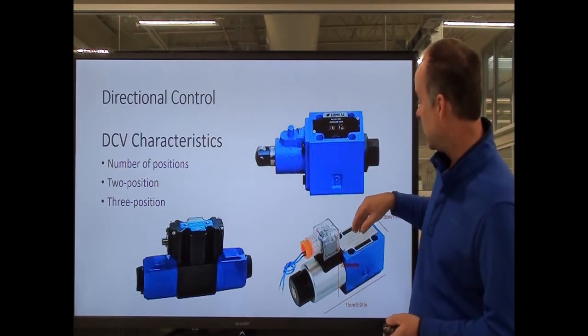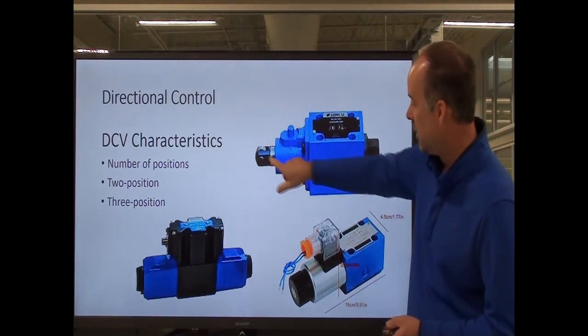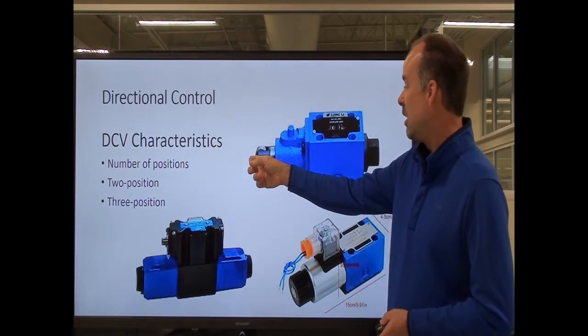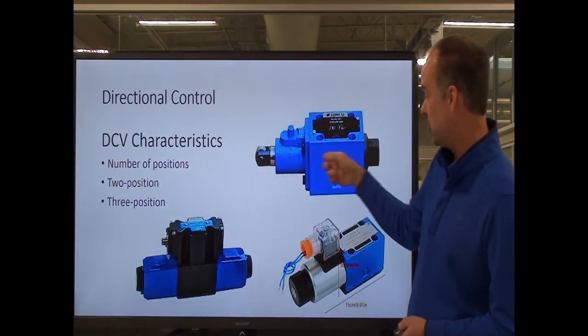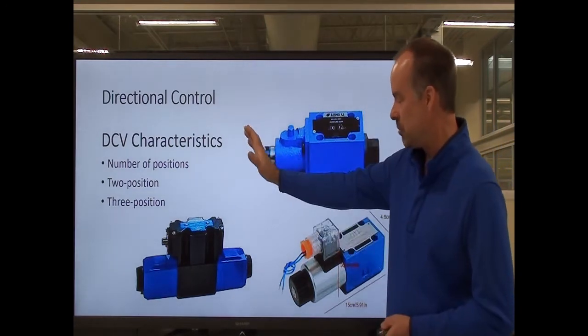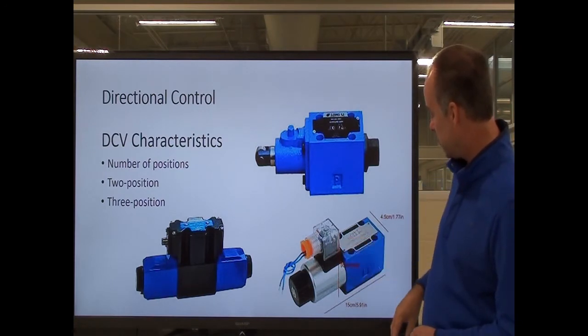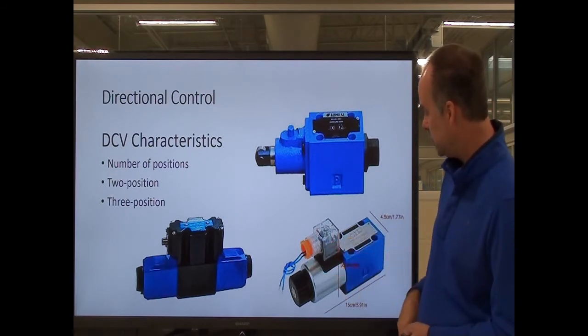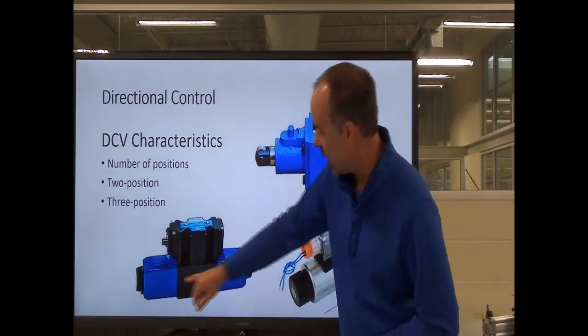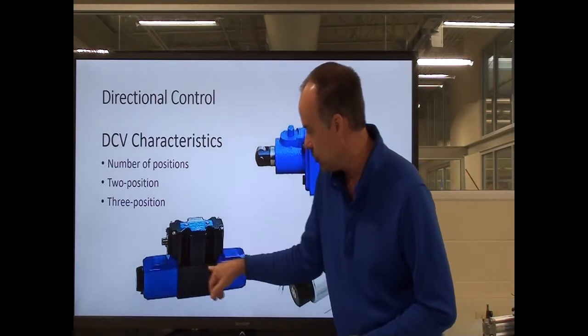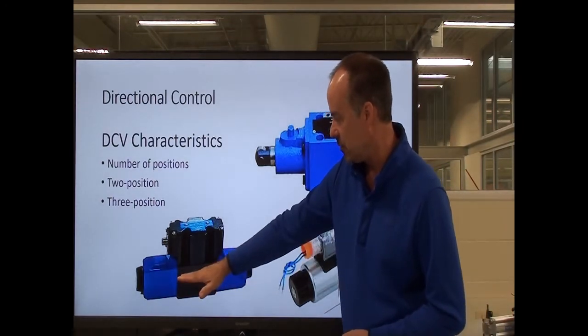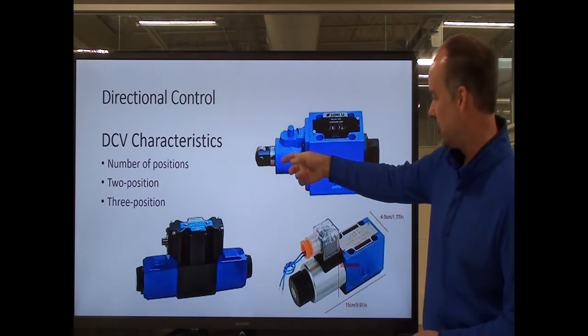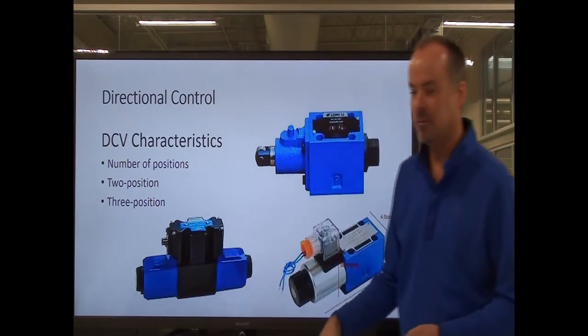This valve back here is cam-operated — some moving piece of equipment would hit this and push it in to shift the valve. This would just be a two-position valve, and then when it came off the cam, the spring would push it back out. Here's a solenoid-operated two-position valve — when I energize this, it creates a magnetic field and shifts the spool. And here I've got a three-position valve because I've got an operator on both sides, so I can shift the valve one way or back the other way, and neither one energized puts it in the center position. You identify whether it's two-position or three-position by the number of operators.